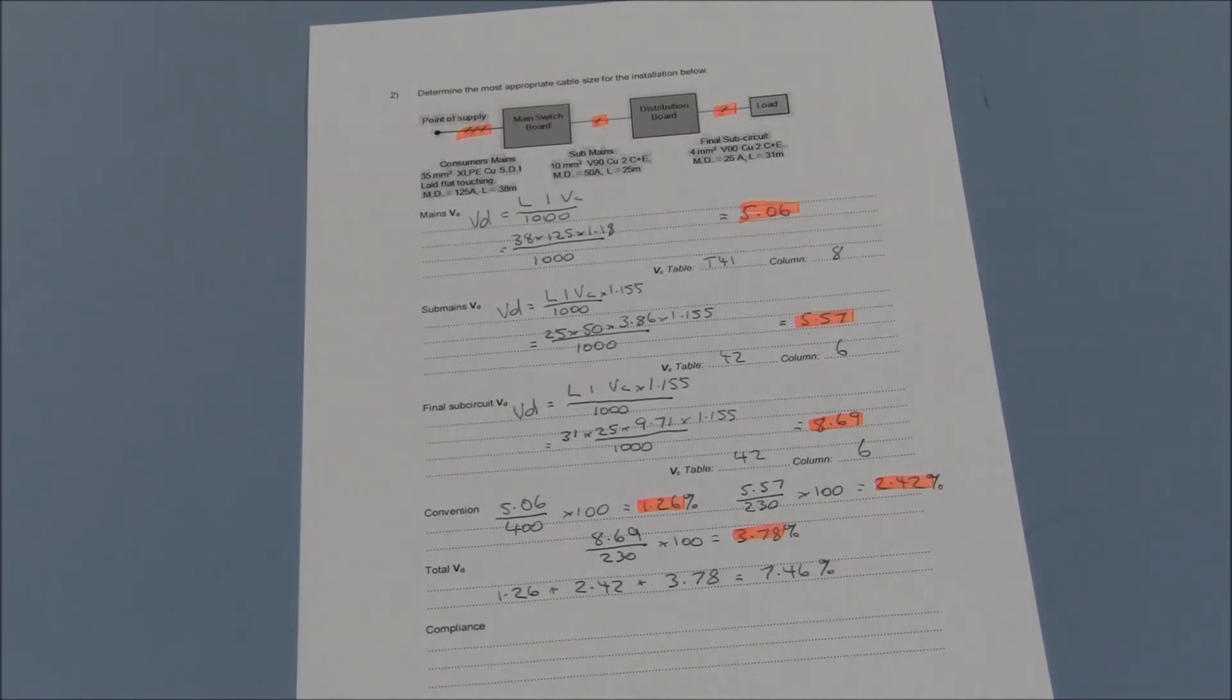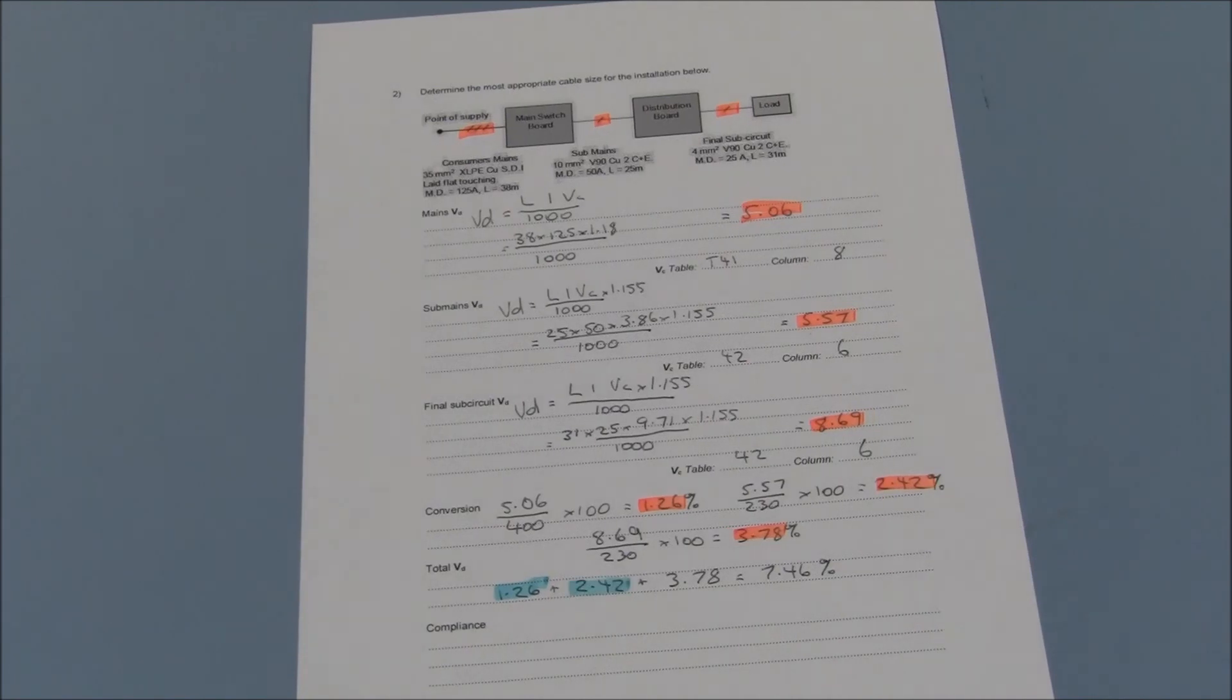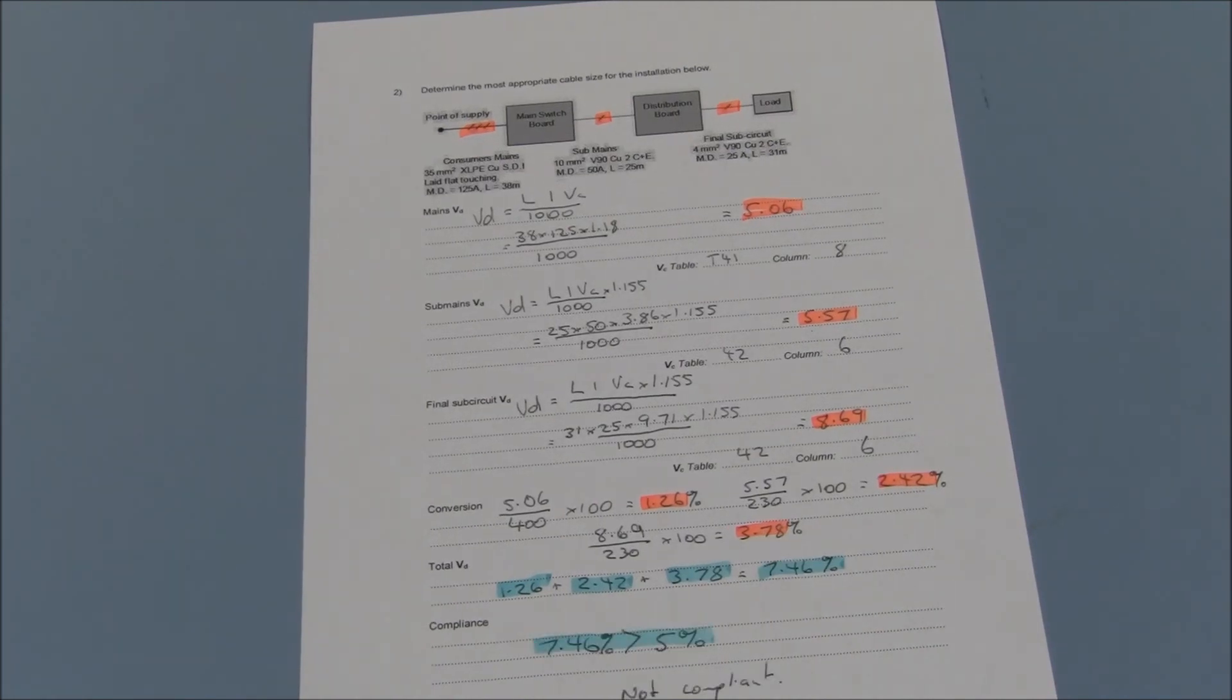1.26% plus 2.42% plus 3.78% equals a total voltage drop across the entire installation of 7.46%. At 7.46%, which is greater than 5%, this is a non-compliant installation.